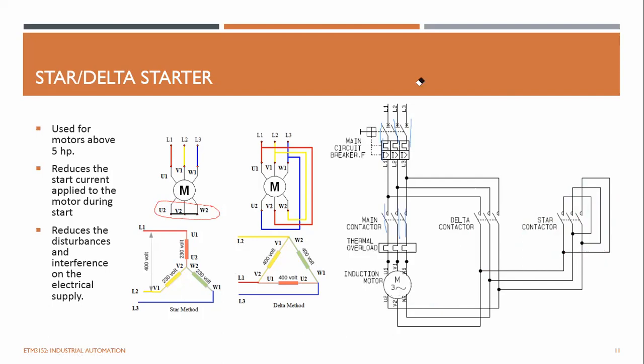And once the motor reaches full load, you disconnect this one and press this delta contactor. So both cannot be pressed simultaneously. There should be some interlock and safety procedure as well, right?